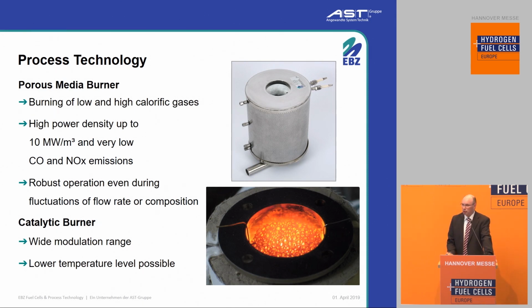In fuel cell systems it's often required to use a heat source like a burner to start the heat-up of a system. At the beginning we can use porous media burners with a high power density. Besides the start burner, it's often required to use a burner for the exhaust gas of the fuel cell, and therefore it's suitable to use catalytic burners, which can also be used for a wide modulation range and for low temperature levels.